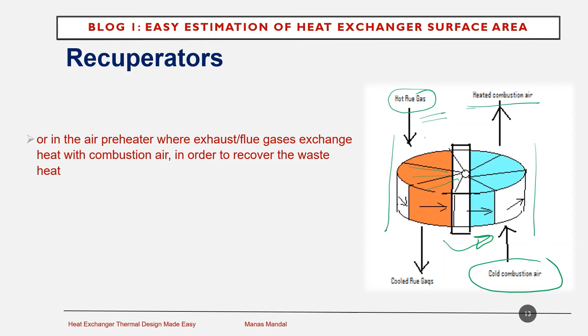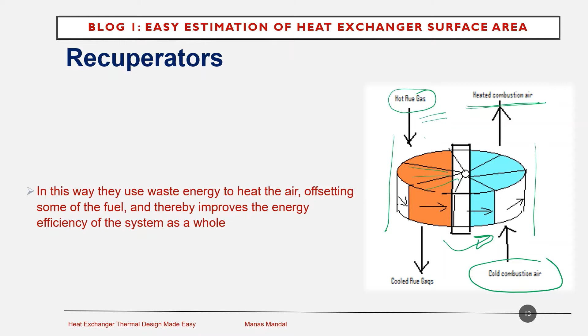Refer to the picture given on the right side, where hot flue gas at high temperature comes to this air preheater, which is a moving drum having a lot of baffles. These baffles get heated by the hot flue gas, and when the drum is moving, these baffles come in contact with cold combustion air and exchange heat to the combustion air. In this process, combustion air gets heated up. In this way, they use waste energy to heat the air, offsetting some of the fuel, and therefore improve the energy efficiency of the system as a whole.